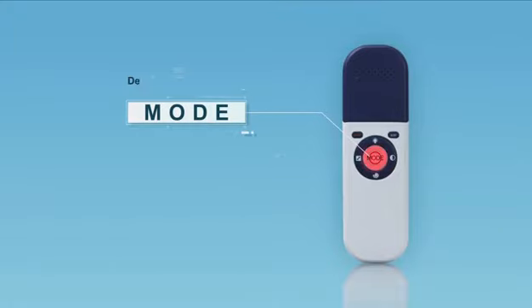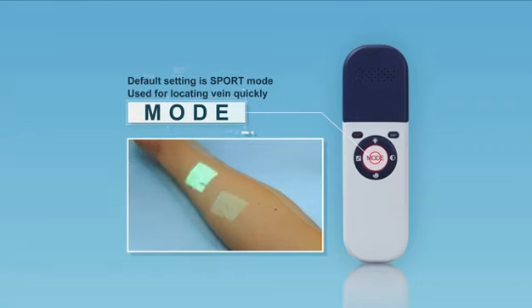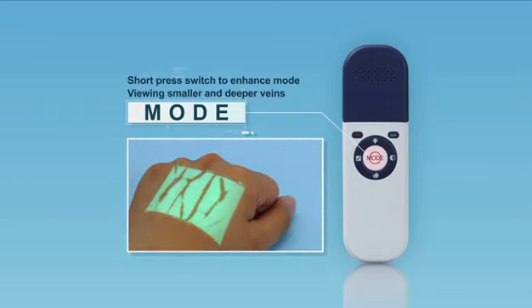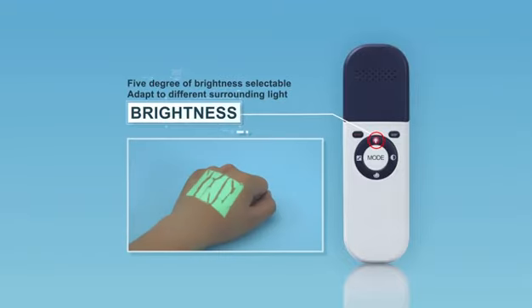Two display modes include Sport and Enhance. Default setting is Sport mode for locating veins quickly. Short press mode button to switch to Enhance mode, which is used for viewing finer image details of smaller veins and deeper veins, especially for pediatrics, obese patients, and edema patients.